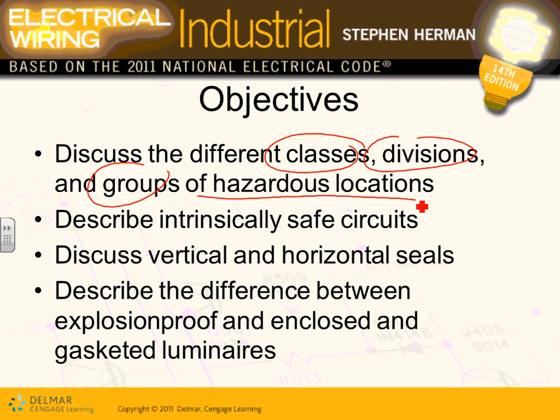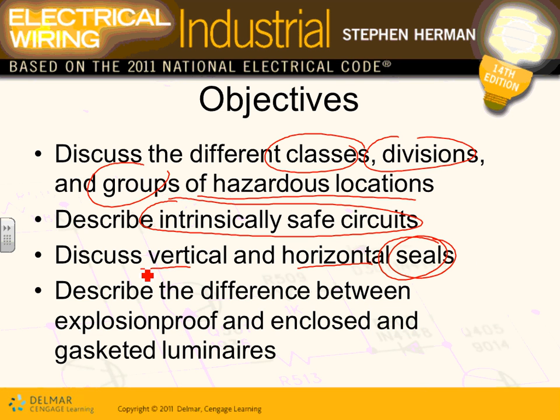That fixture here cannot be installed in a hazardous location. It has to be a special type of fixture, special types of switches, special types of power, which cost you an arm and a leg. That's why we care about these. You'll see them in a second. There's something called intrinsically safe circuits. These are low voltage electronic circuits that they use because they don't create fire. There are also seals, horizontal and vertical, that you have to install in hazardous locations.